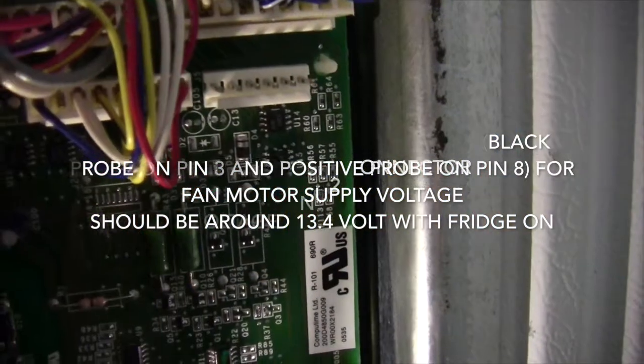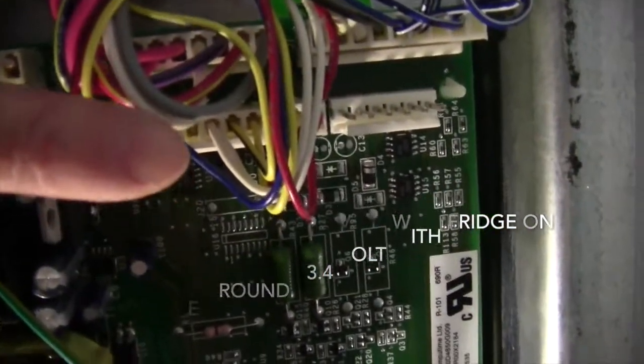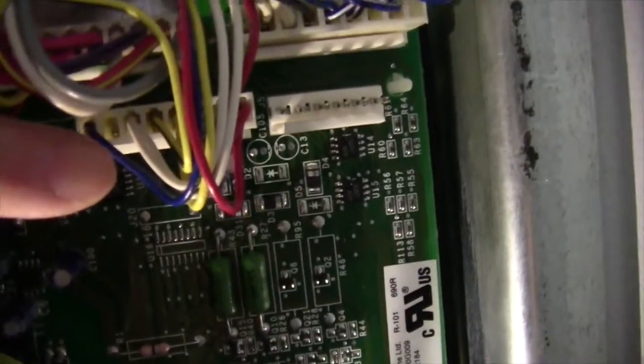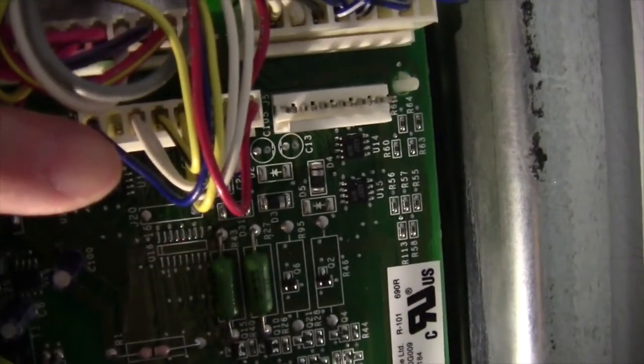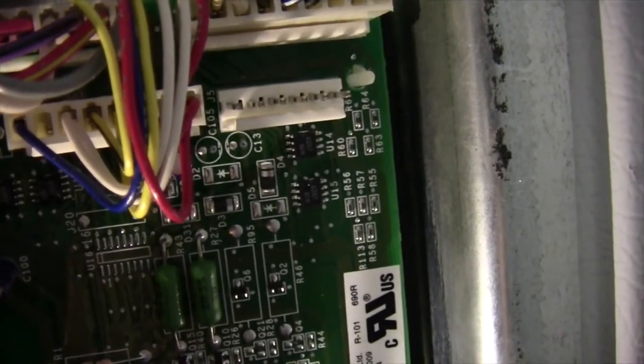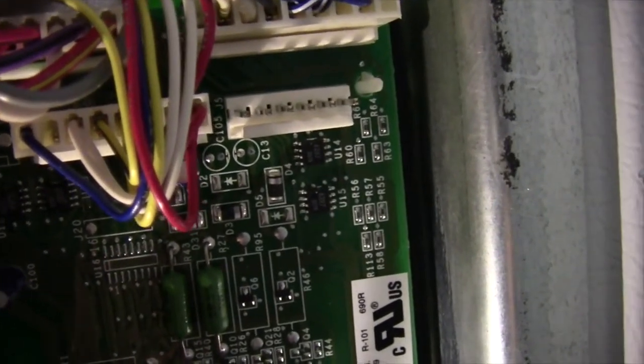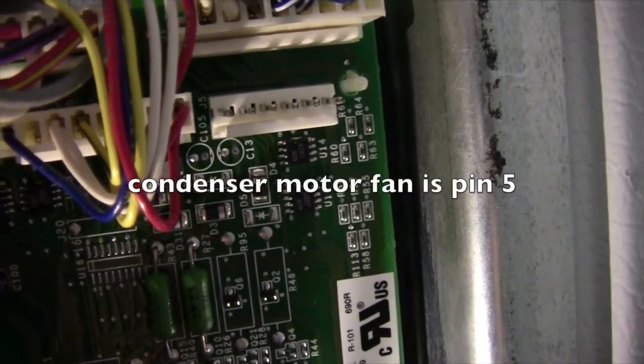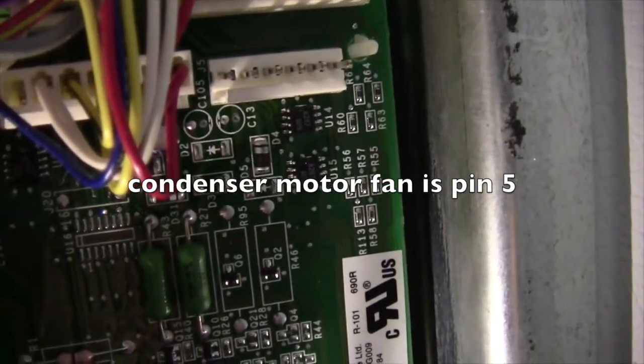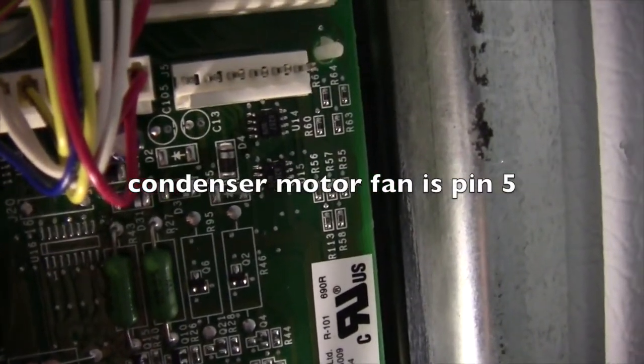The J2 common terminal is pin number three, and then four is for the evaporator fan. If you want to check for the condenser motor, this should be number five.